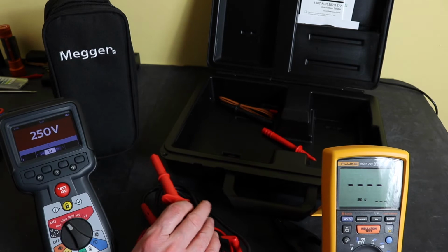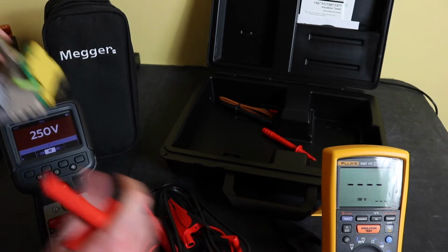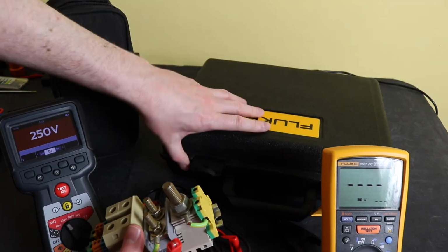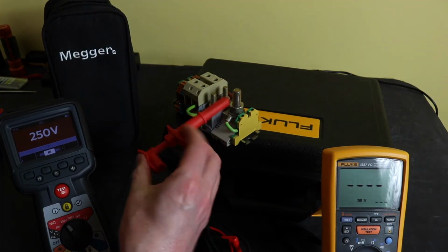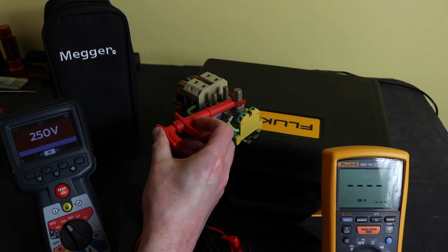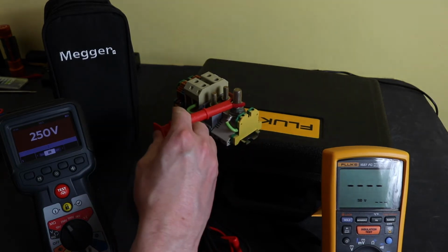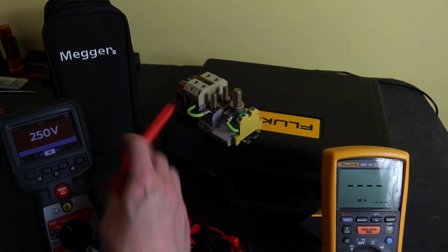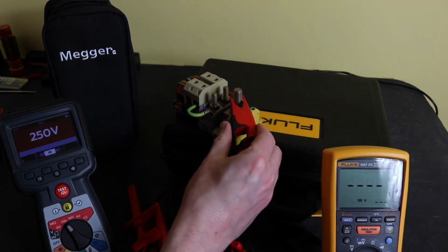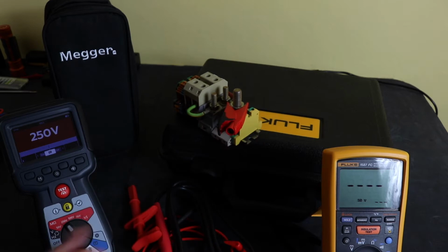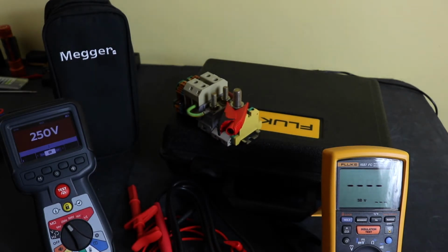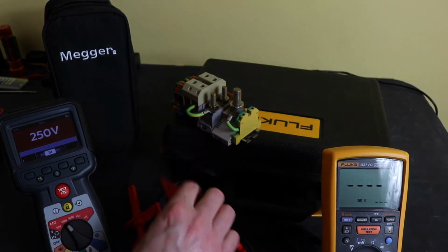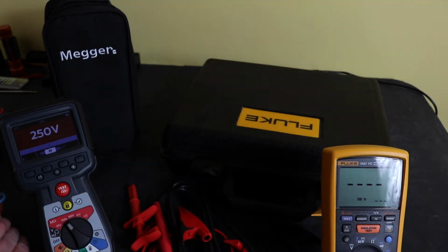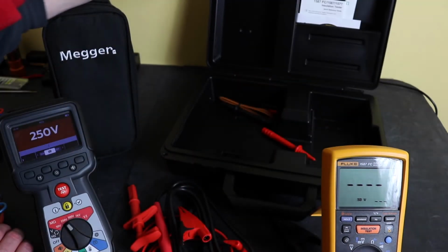And we can show that if we get on here, twiddle it down for a few seconds. And you can see here, I've got the M12 bolt here, pretty much on its maximum there for the Megger, and you won't get it around the nut at all. Whereas with the Fluke, it easily goes on the bolt and will also fit onto the nut as well. So yeah, I do prefer those to what the Megger has.